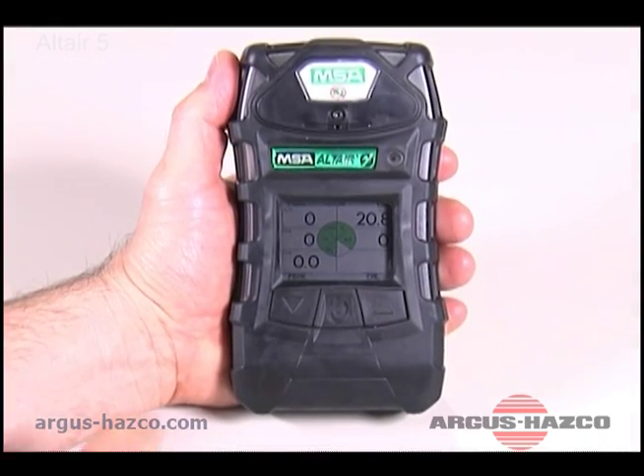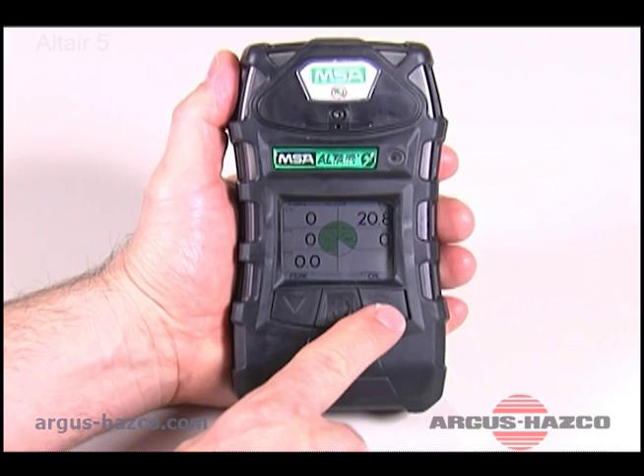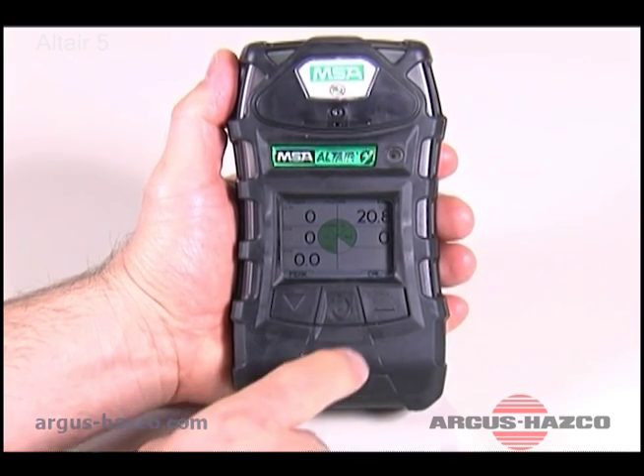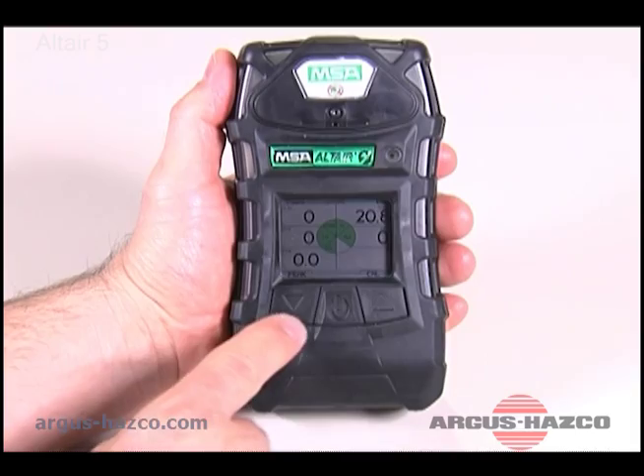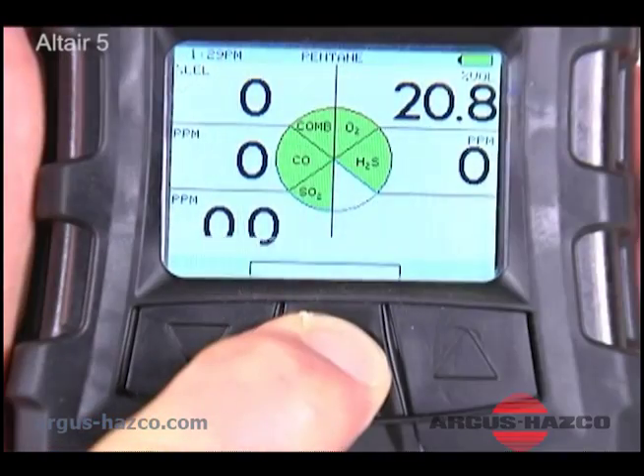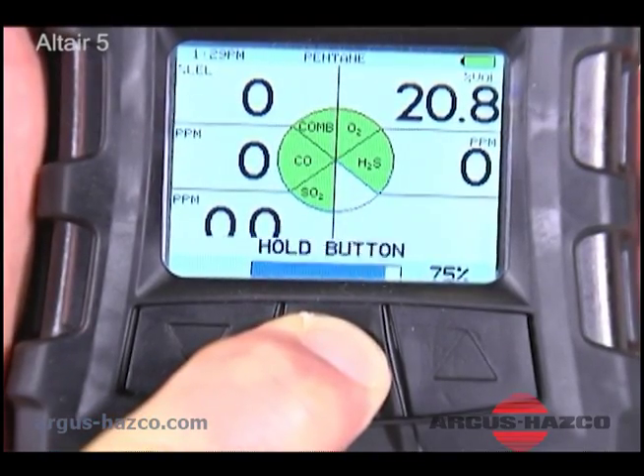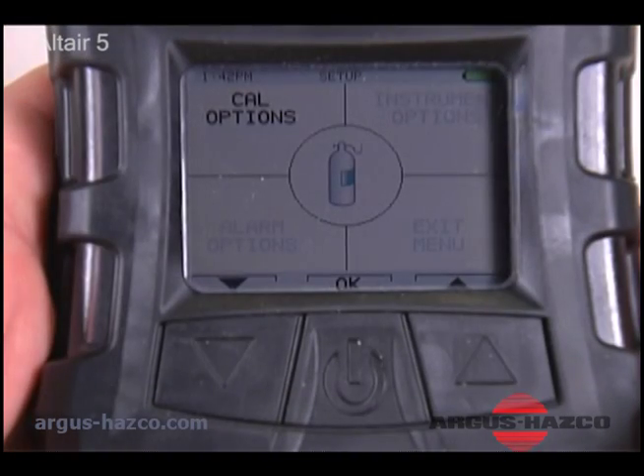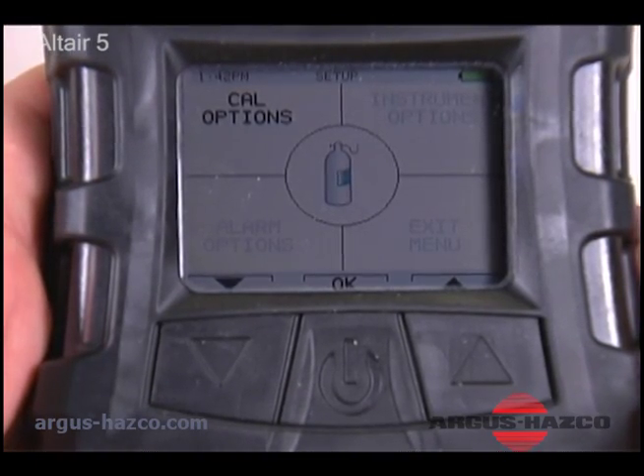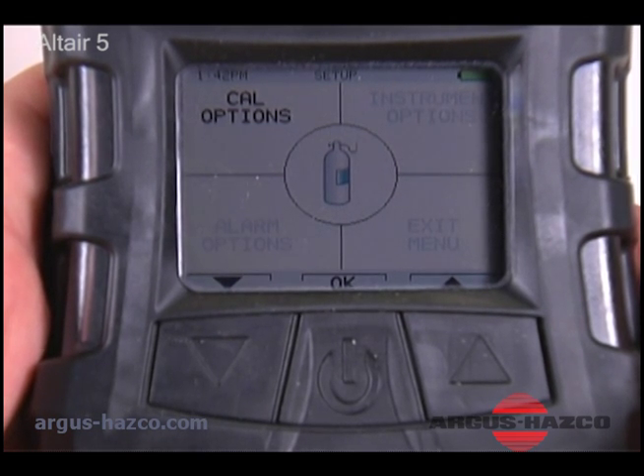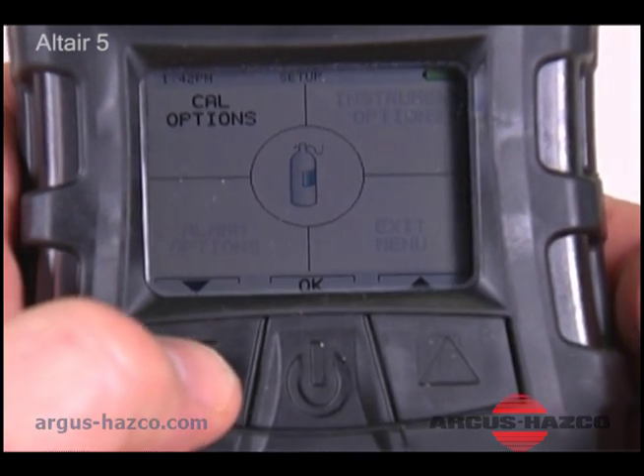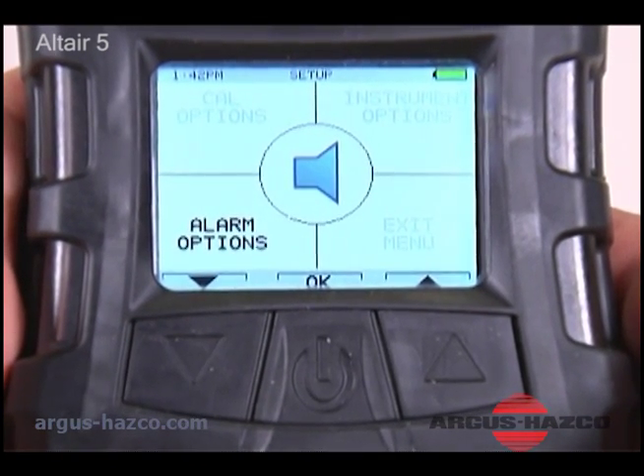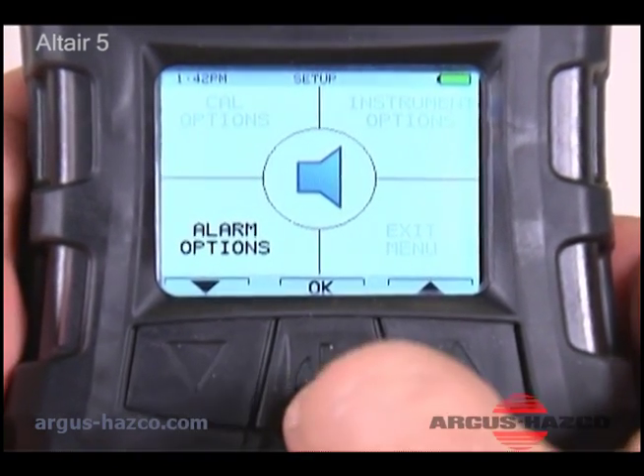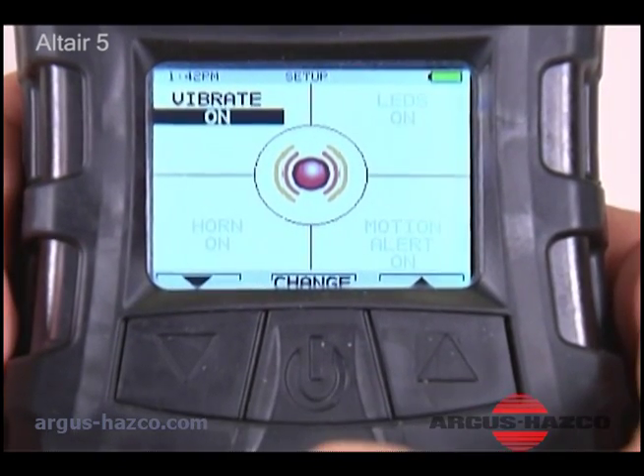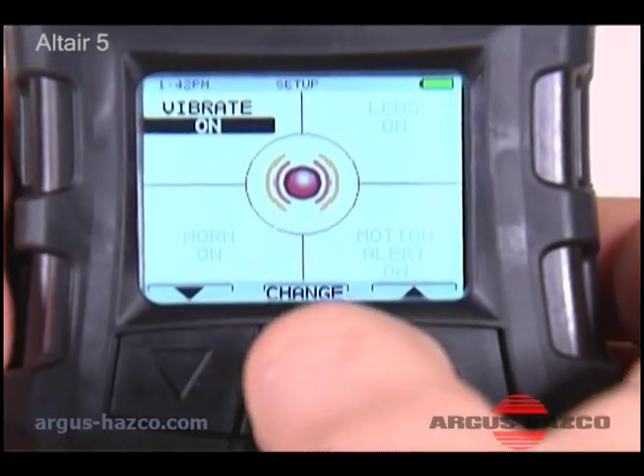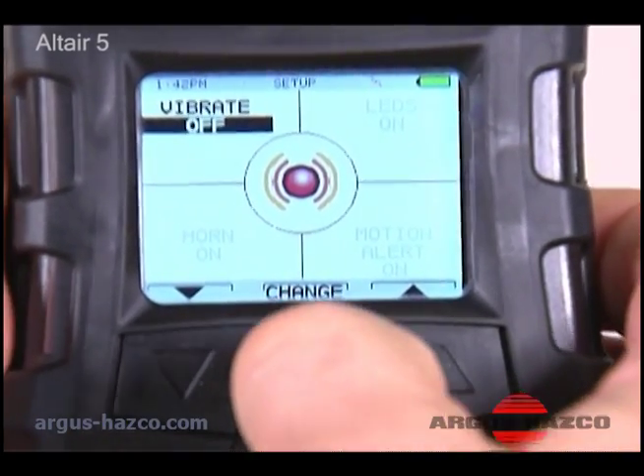The Altair 5 is menu-driven using 3 function buttons. The on-off button turns the instrument on and turns the backlight on in measurement mode. To turn the instrument off, press and hold the on-off button for about 4 seconds. In the Setup menu, use the on-off button to enter selections. For example, to turn the vibrating alarm on or off, press the down arrow button to move forward through the menu to alarm options. Press the on-off button to select Vibrate. Then use it to toggle between on and off.